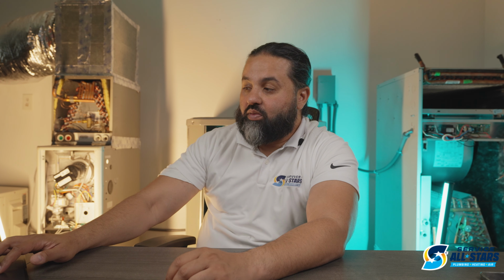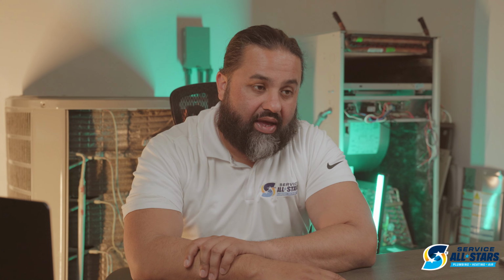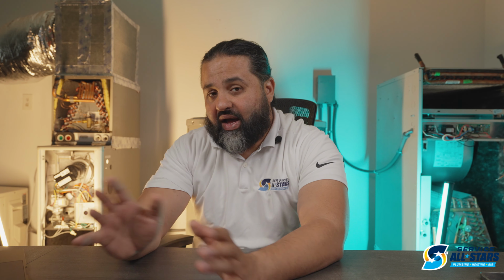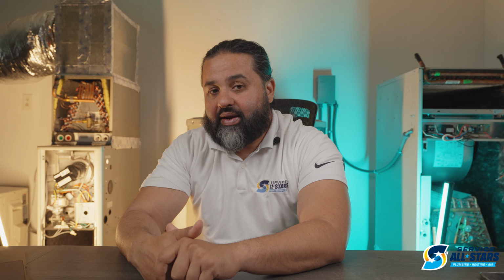I know if I was to buy a system, I would want it to work at the optimal level so I get the most comfort that can be provided to me inside of my home. And I can't tell you how many clients I've seen that had their system installed and still it's somewhat effective in their home, but not where it needs to be. There's hot and cold spots. So that's another thing. If you have high static pressure, you're going to have hot and cold spots inside of the home. And you're going to have one section of your house hotter than the other section or cooler than the other section. And that really comes down to the air delivery system not being designed properly.